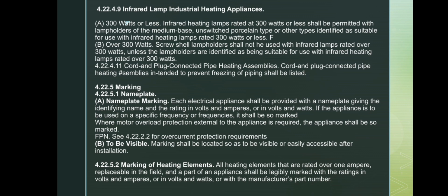All appliances must have a nameplate showing the identifying name, voltage, and either amperes or watts, and if it operates on a specific frequency, it must be marked. If the appliance needs external motor overload protection, this must also be indicated. The nameplate must be placed in a location that is visible or easily accessible after installation.